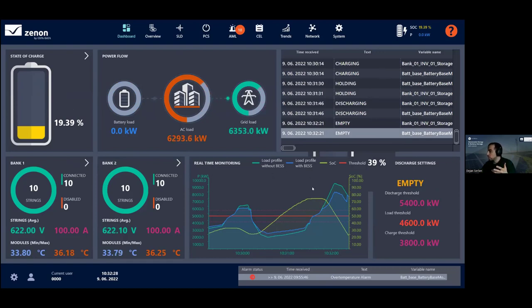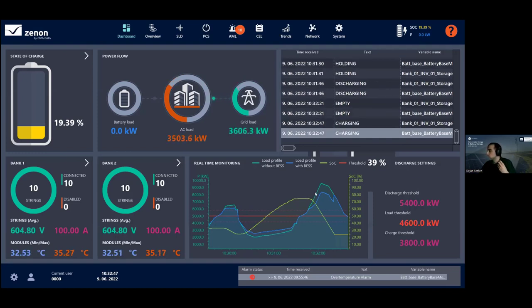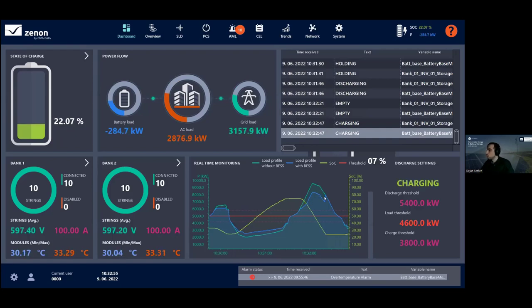On the widget down here we can see our trend - real-time monitoring of our battery. The green line represents battery storage capacity, almost full here, and when the load profile rises through a certain limit, the battery starts discharging, and we see a load profile without it.